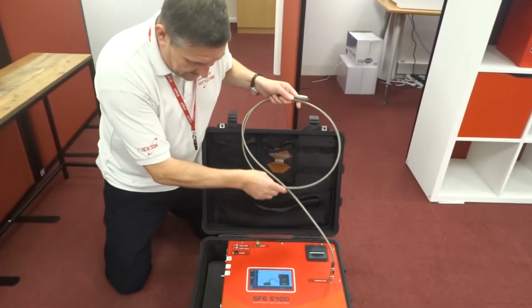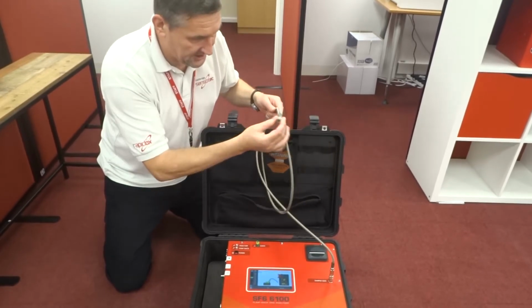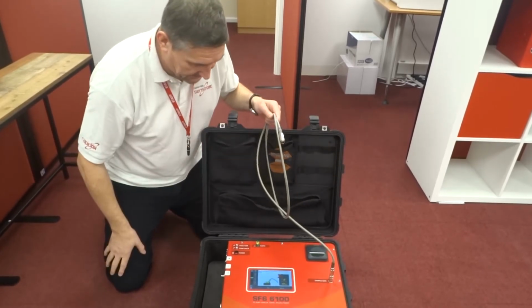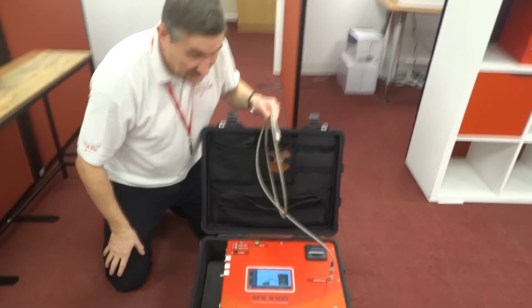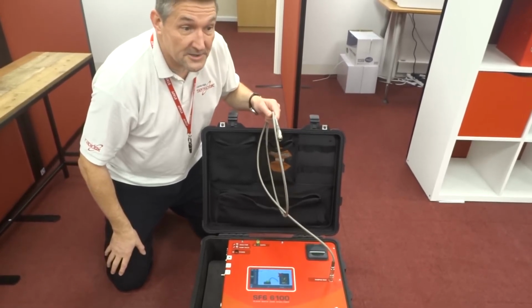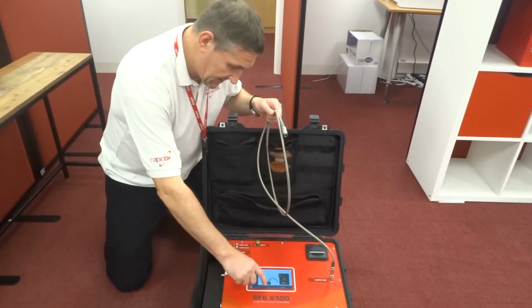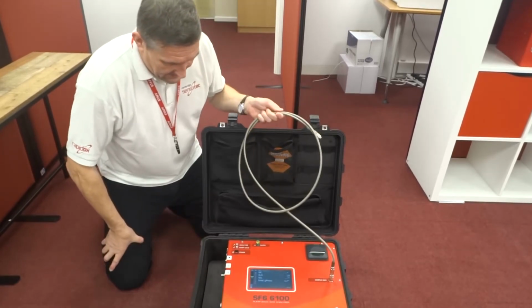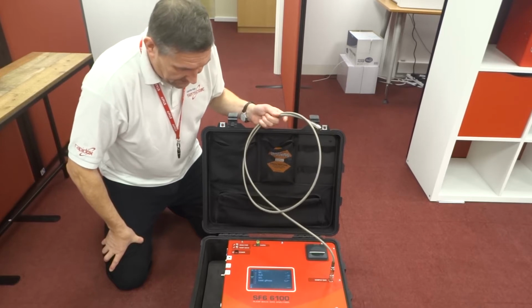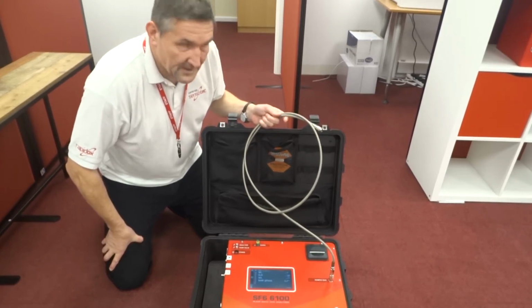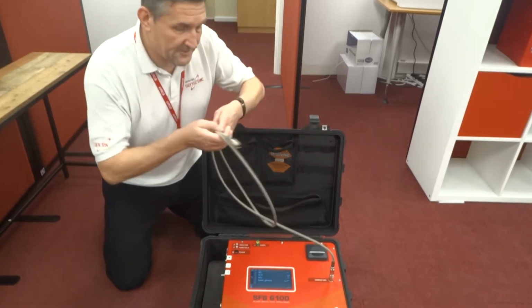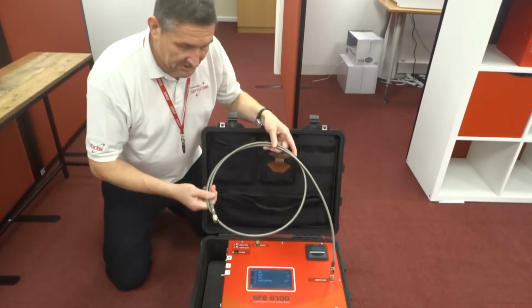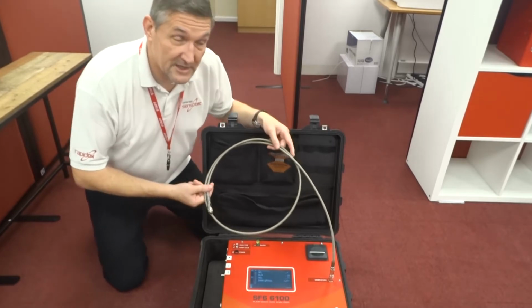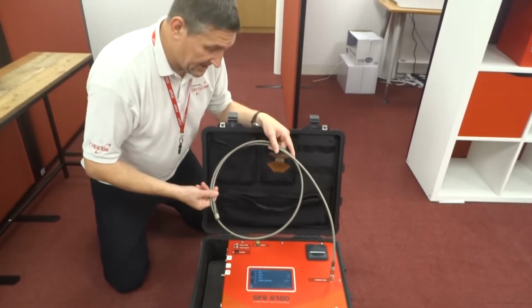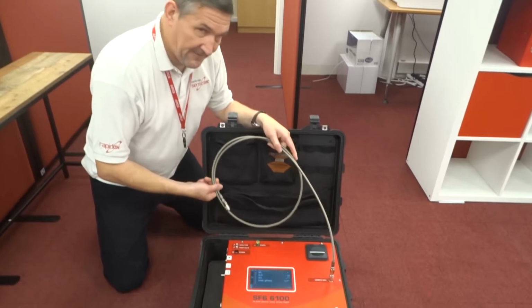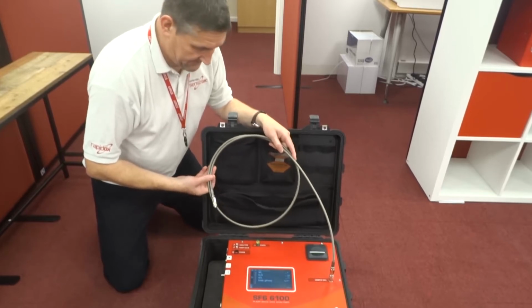You get a message on the screen telling you to not connect this to the other end of a switchgear because you will vacuum out the entire contents of your circuit breaker if you are not careful. So we'll press OK, and the machine will wait a moment and then the pump will run. It's vacuuming out the hose now, and this will help to get any moisture out of the hose or any remaining SF6 or even nitrogen or any other gas, and it takes about 45 seconds to complete.